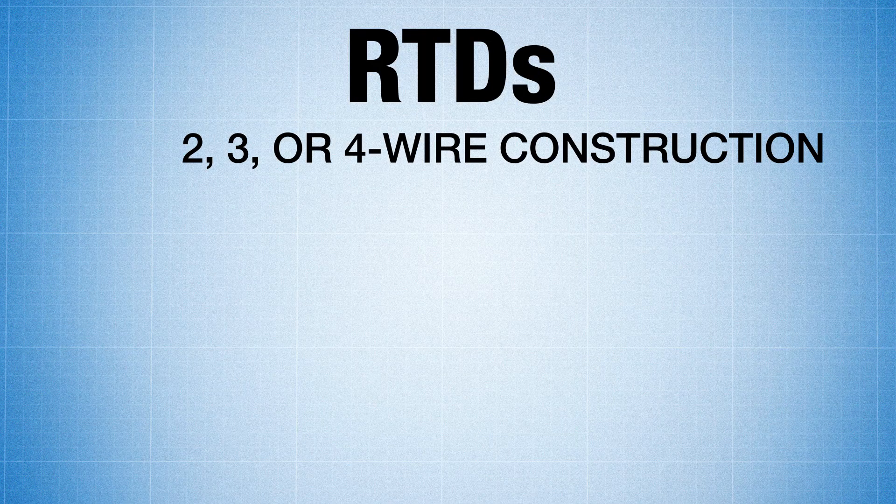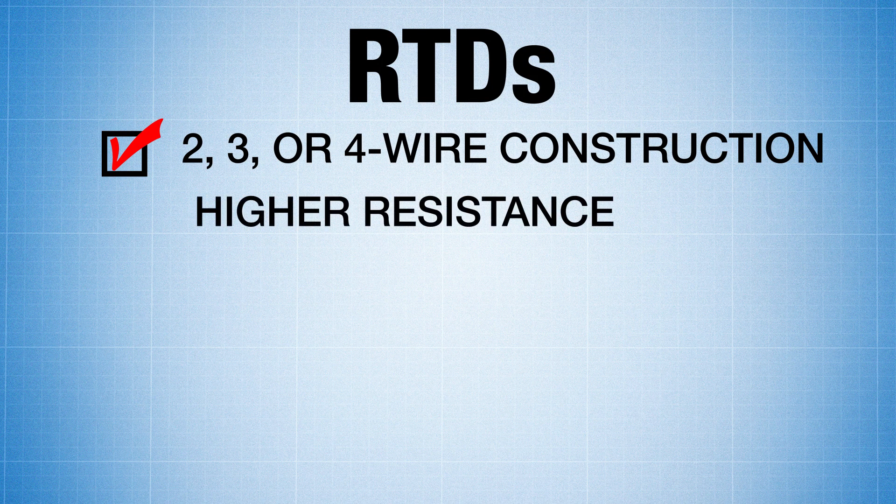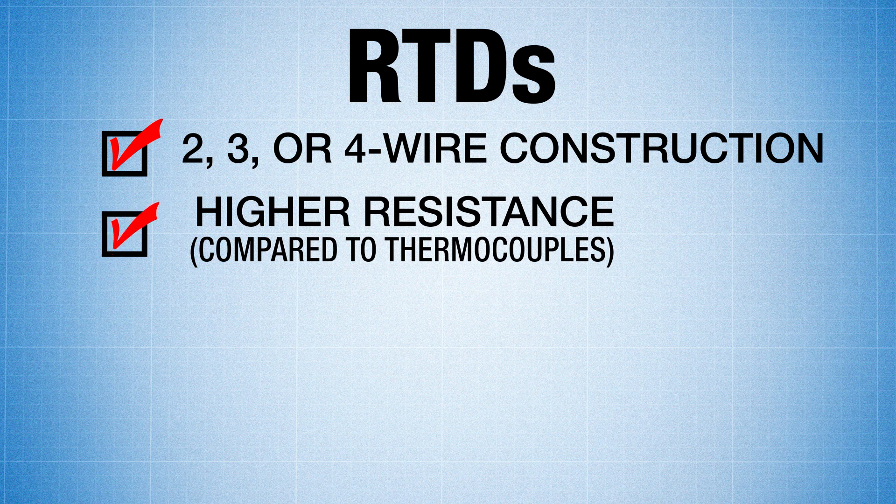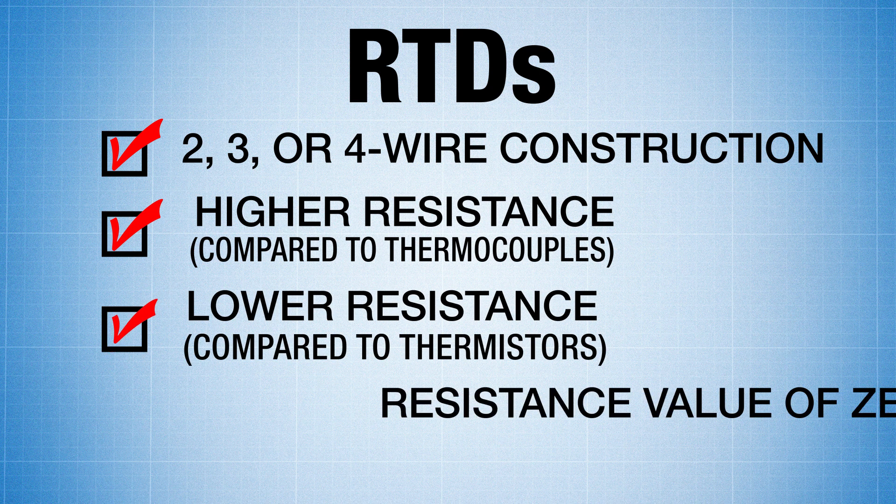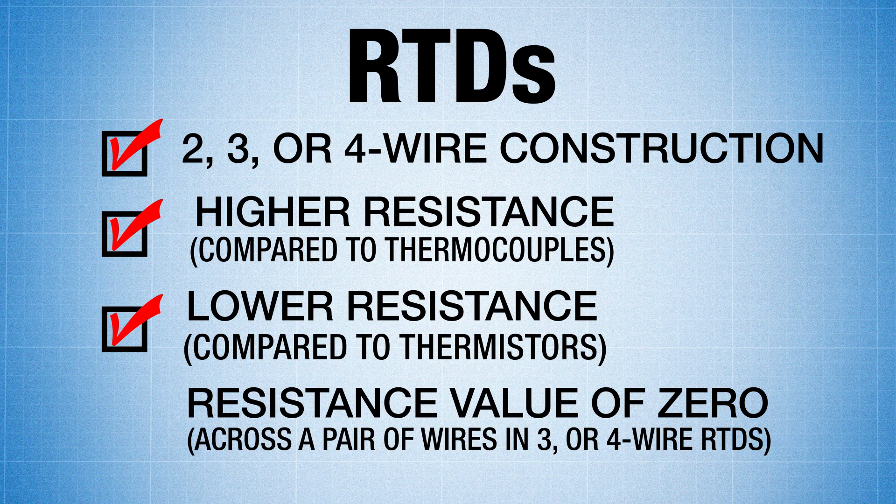RTDs can come in a two-, three-, or even a four-wire construction. They have higher resistance compared to thermocouples and a lower resistance compared to thermistors. Resistance value of zero across a pair of wires in a three- or four-wire construction.